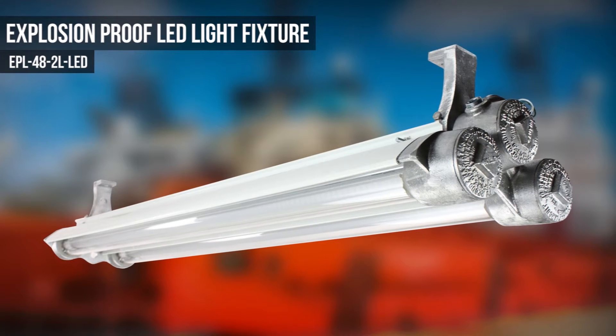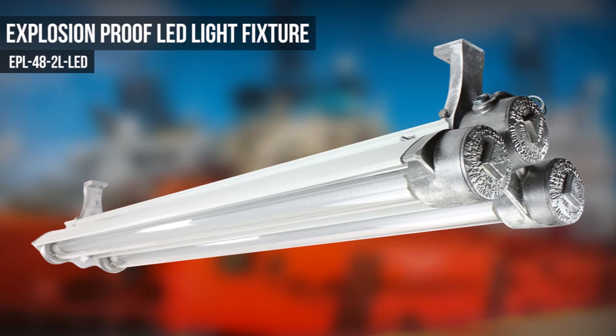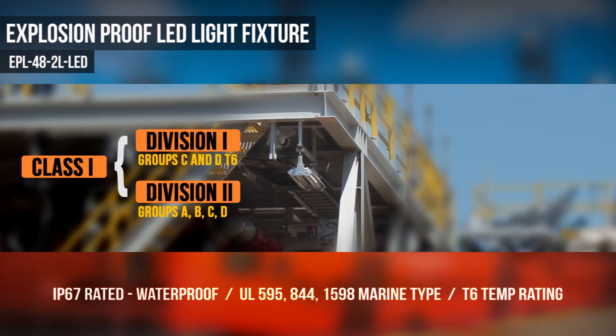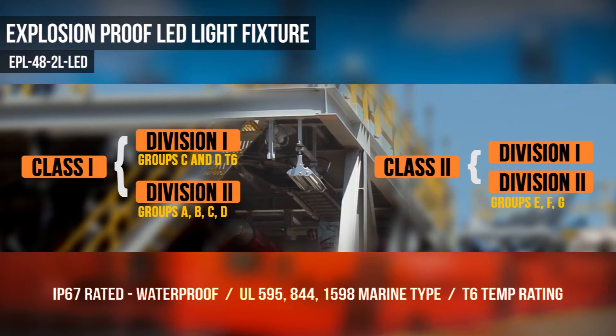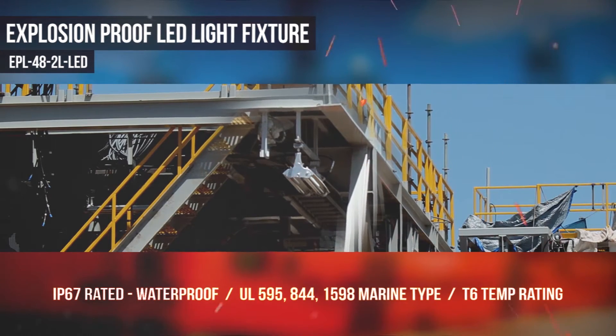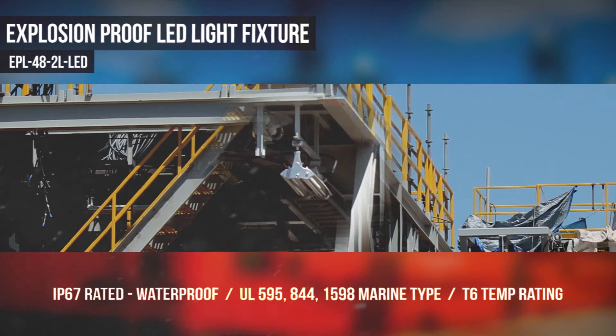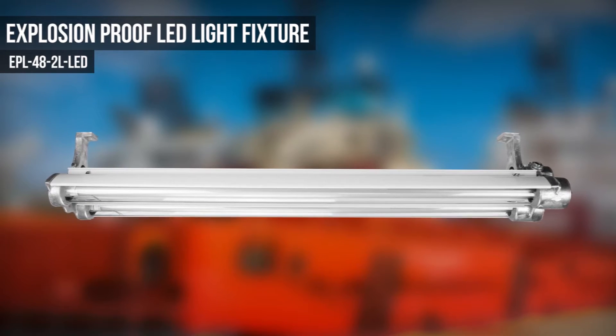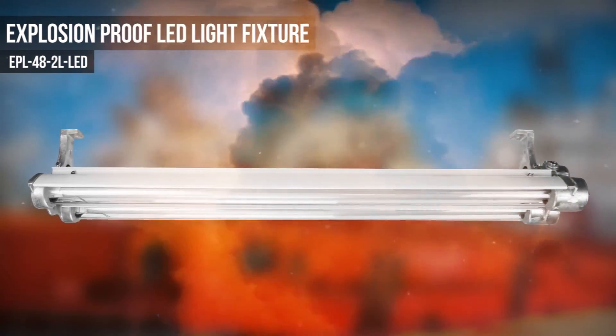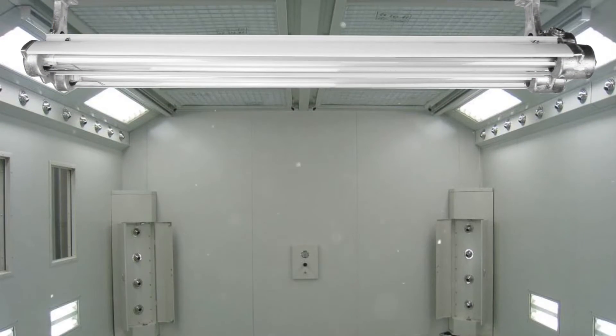The Larsen Electronics EPL-48-2L-LED LED Flame Proof Explosion Proof LED Light Fixture is United States and Canada approved, Class 1 Division 1 and 2, Class 2 Division 1 and 2, for areas where flammable, chemical, petrochemical vapors, dust, fibers, or flyings exist or have the potential to exist. This 4-foot linear 2-lamp IP67 dust proof, waterproof, and explosion proof LED light fixture has a T6 temperature rating and carries a paint spray booth light certification.